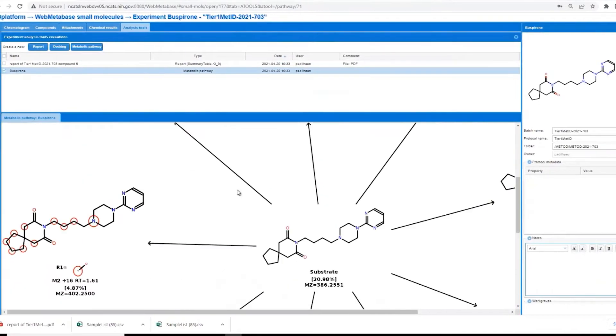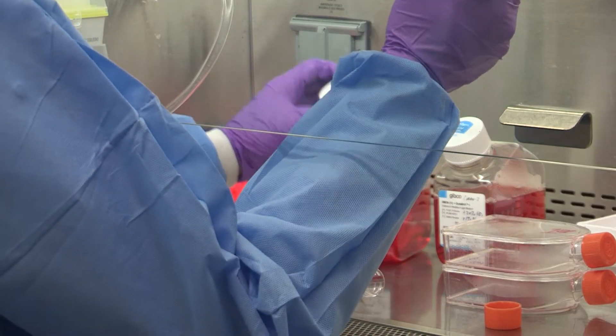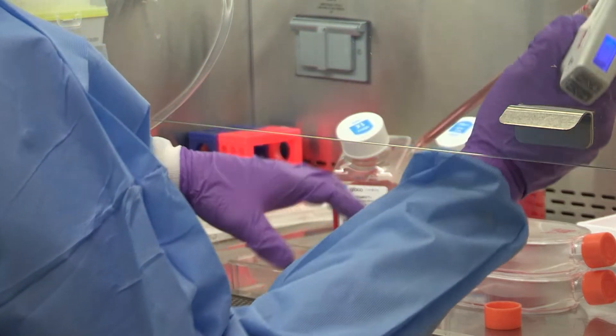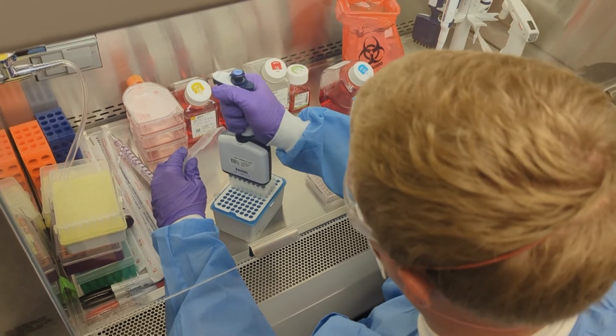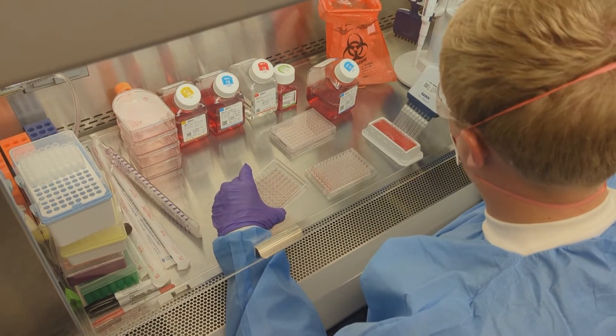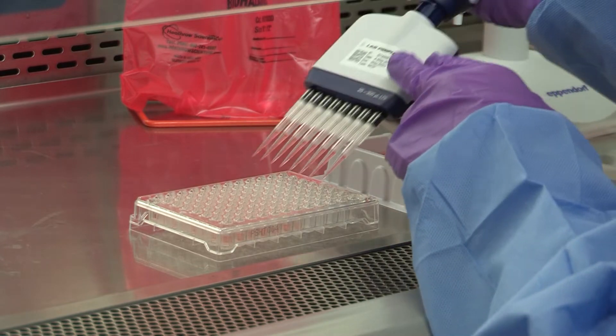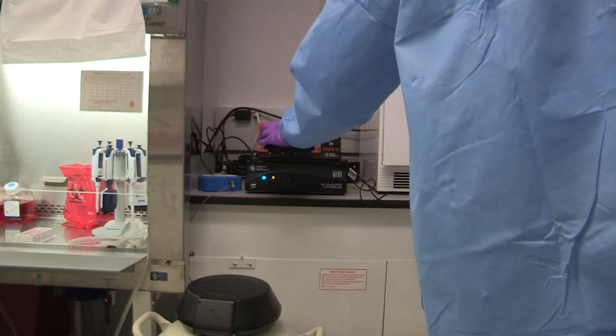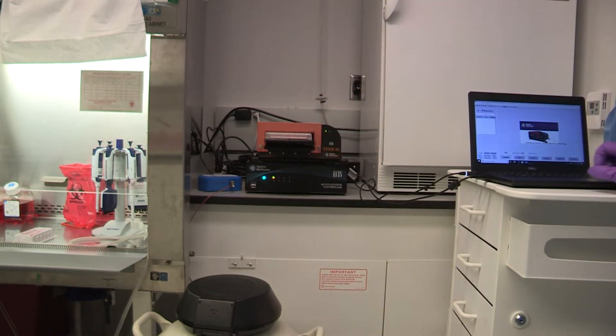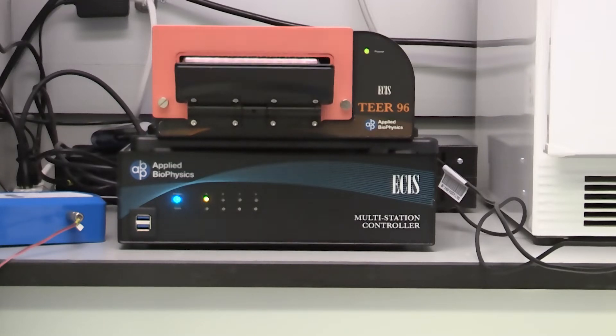The cell culture lab is where we conduct cell-based studies for Tier 2 assays. We routinely run Caco-2 and MDCK MDR1 cell-based assays to assess passive permeability and efflux transport, which is very important in determining the fate of the compound in the body. Cells are cultured in 96-well transwell plates, and these assays for discovery compounds are also performed using the automated TECAN platform. To ensure the formation of monolayers of cells on the donor side of the transwell, a special device is used to measure the transepithelial electrical resistance, or TEER, for short. Working with Applied Biophysics, we have developed the automated TEER 96 measurement device. This device reads the resistance of each of the 96 wells in less than 2 minutes and stores the data electronically. The device can also read TEER continuously to assess barrier function and integrity over time.